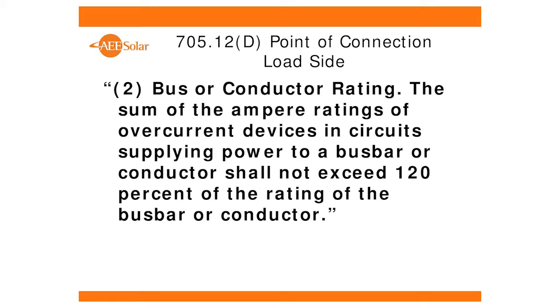And here's where Mr. Wiles wrote his article and kind of threw everybody into a tizzy on this one. It says the sum of the ampere ratings of overcurrent devices in circuits supplying power to a bus bar or conductor shall not exceed 120% of the rating of the bus bar or conductor. Well, the problem is that it's a thermal issue with bus bars. It's not an issue at all with conductors, because it has to do with an enclosure, a panel board that has a bunch of heat being created by circuit breakers. And so the 120% rule is talking about, well, how much heat are you allowed to add to this panel board, which has been evaluated for certain things. And so the 120% was a fudge factor that was only allowed to be used for residential without any respect to where the breaker went relative to the service utility feed.